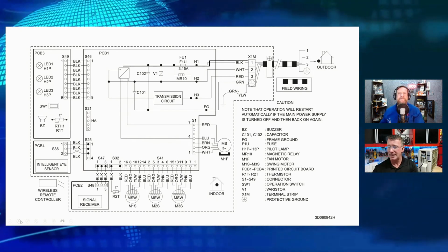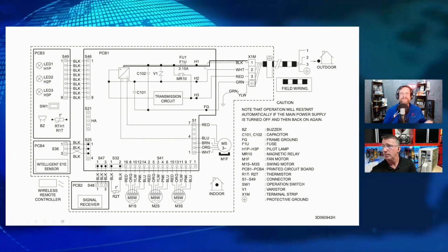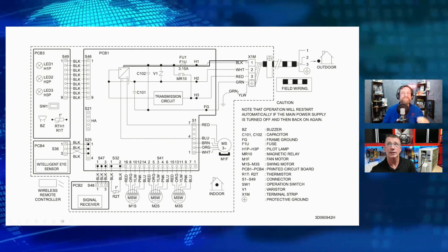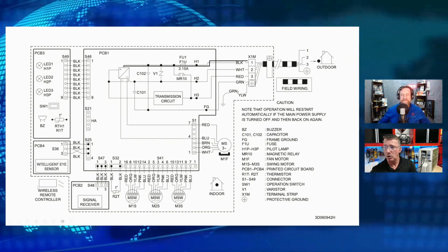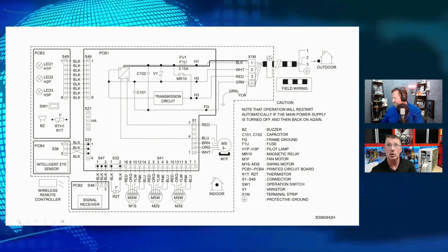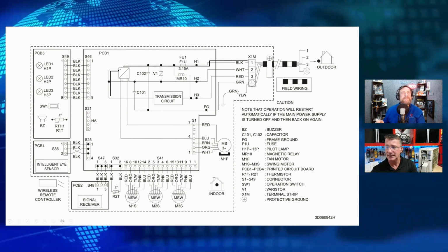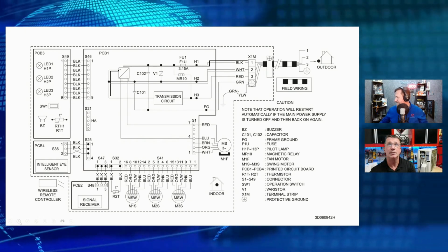So I'm bringing that single phase AC in on number 1. I'm going to feed it into our AC to DC rectification circuit inside that indoor control board. Now, let's continue to follow this all the way because it'll help you understand what's happening on that signal wire, as a lot of people call it, or number 3 wire, because it's actually part of an entire circuit.